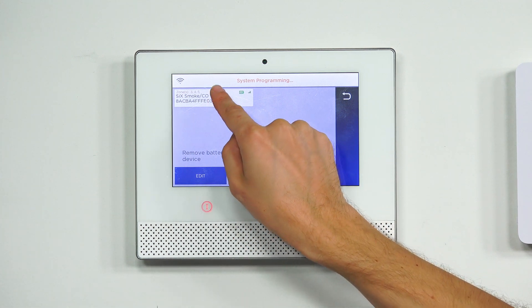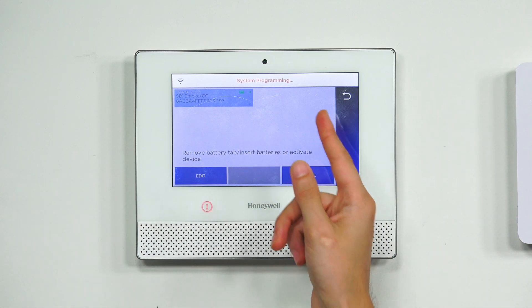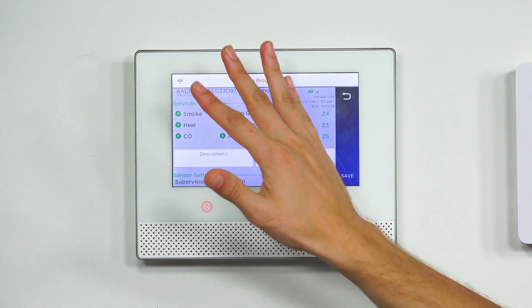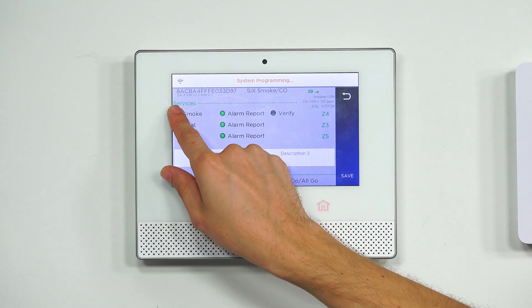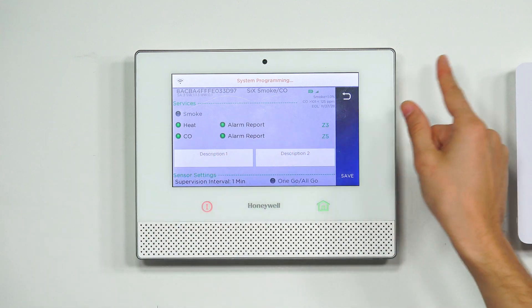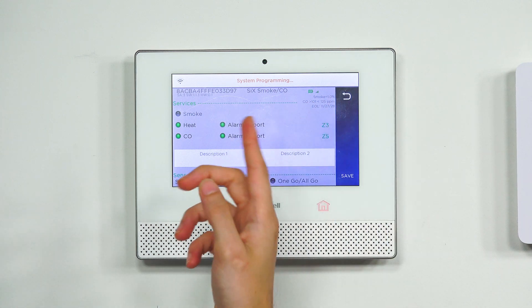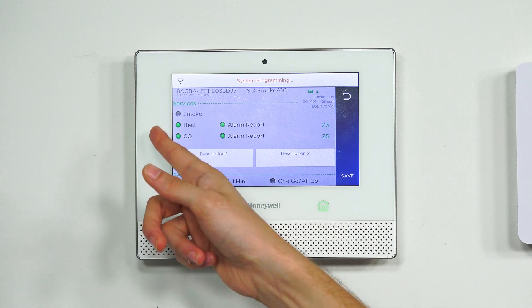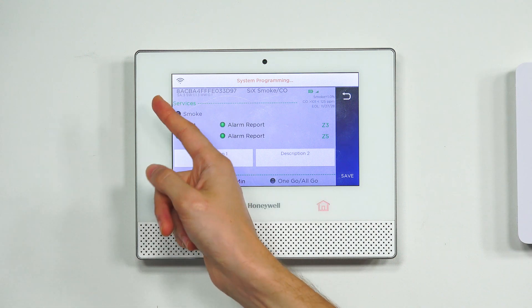We press the button for the sensor — it's highlighted blue — and then press Edit in the bottom left corner. We get to the Programming screen where we can configure various settings for this SiX Combo device. Let's say I wanted to turn off Smoke — we press the button and the option goes away. We no longer have the Alarm Report or Verify function because we've turned off smoke detection. When it's gray, it's off; when it's green, it's on. Right now we have Heat Detection and Carbon Monoxide Detection, but not Smoke Detection.